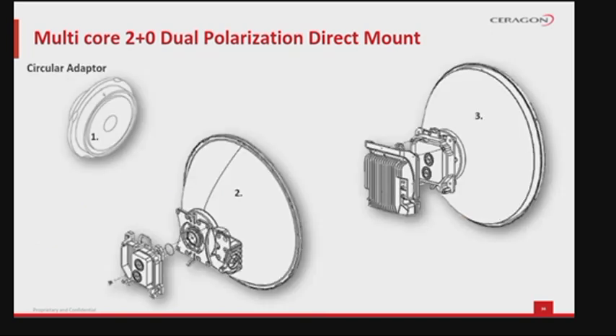Now, for the actual steps for 2+0 dual polarization direct mount. 1. Prior to the installation, follow the antenna manufacturer's instructions to use the circular adapter. Remove the existing rectangular transition, swap the O-ring, and install the circular transition instead.